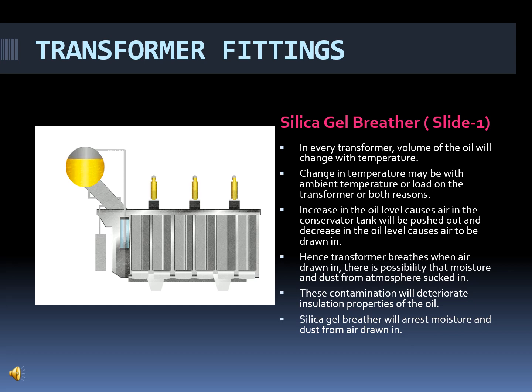So what happens? An increase in the oil level causes the air in the conservator tank to be pushed out, and a decrease in the oil level causes air to be drawn in. Just look into the graphical image I have enclosed here. Just see the graphics, and hence the transformer breathes. When air is drawn in, there is a possibility that moisture and dust may enter the conservator from the atmosphere. This moisture and dust will deteriorate the insulation properties of the oil if it enters directly without a silica gel breather. Hence the silica gel breather is useful in arresting the moisture and dust from the air which is being drawn in.